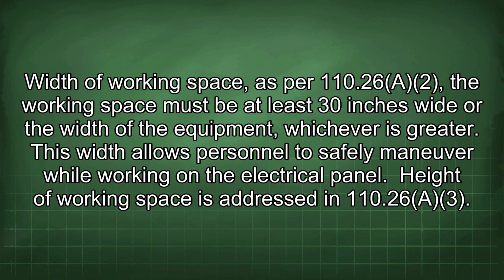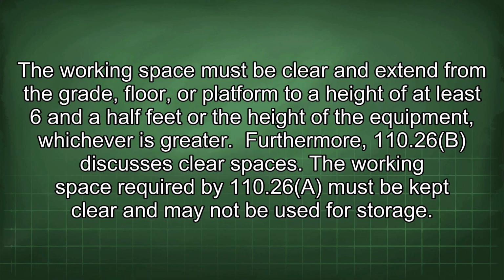Width of working space, as per 110.26(A)(2), the working space must be at least 30 inches wide or the width of the equipment, whichever is greater. This width allows personnel to safely maneuver while working on the electrical panel. Height of working space is addressed in 110.26(A)(3). The working space must be clear and extend from the grade, floor, or platform to a height of at least 6.5 feet or the height of the equipment, whichever is greater.